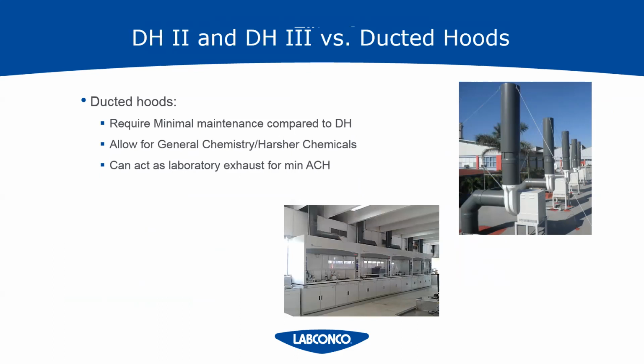So a ducted fume hood can act as a laboratory exhaust to meet minimum air changes per hour. Let me explain this. The air changes per hour: every building, even your office space, any kind of building, even your house, has a minimum air change rate that an organization called ASHRAE calls out. Labs require a little bit more than your standard office space because they take into account the fact you're working with chemicals and things that you don't want to be breathing in.